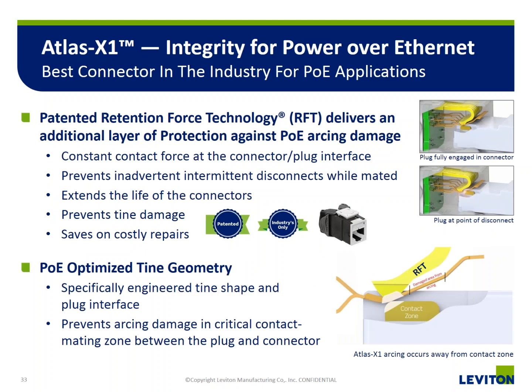Another thing to consider with PoE is the concept of a powered disconnect. If anyone's not familiar with how PoE works, part of the IEEE standard for PoE requires that the power source, the PoE switch for example, is not allowed to pass power through the cabling until it has had a conversation, or handshake, with the device to confirm not only "yes, I am a PoE device," but what type of PoE it can handle. So if the device says it's only a Type 2 PoE device, then the maximum amount of power that the source is going to provide is 30 watts.